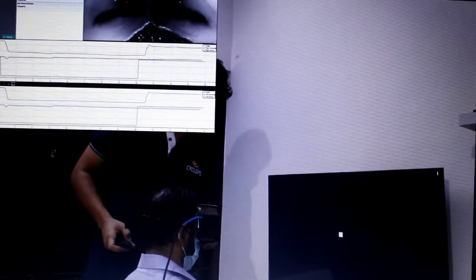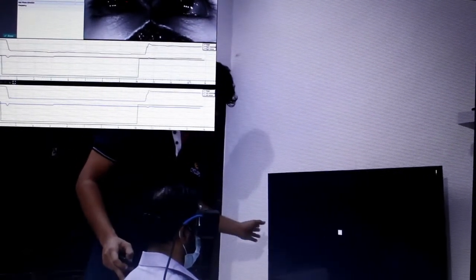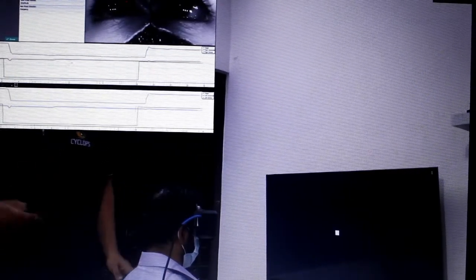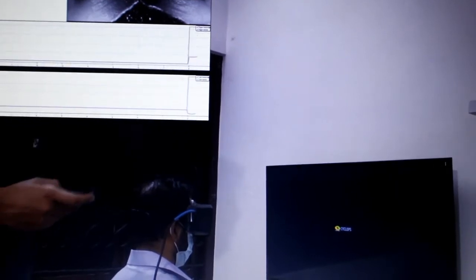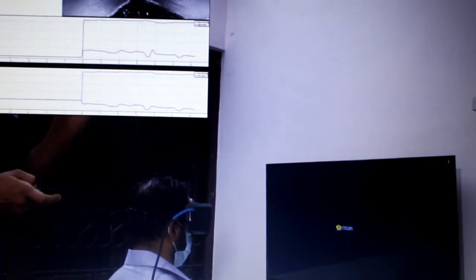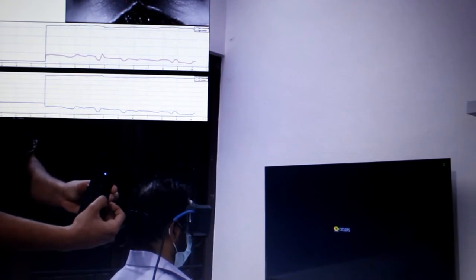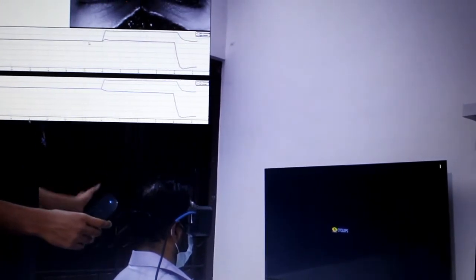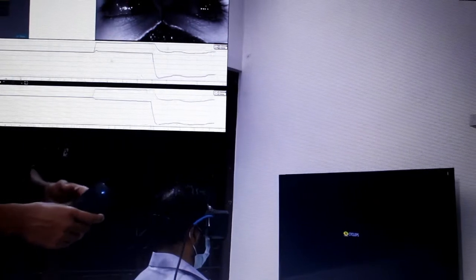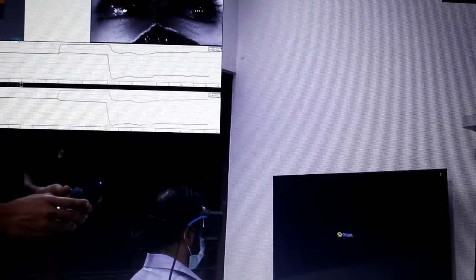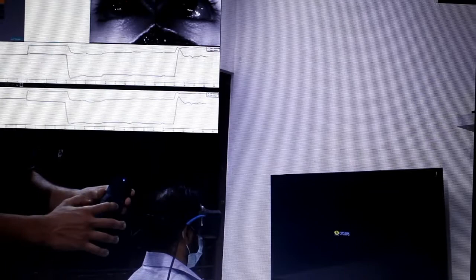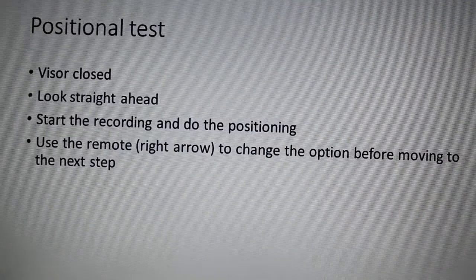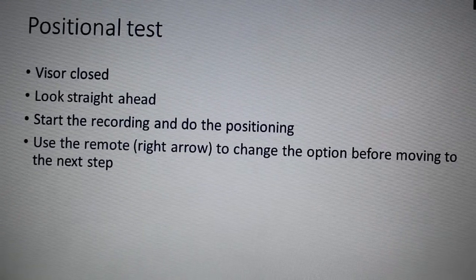For the without-fixation gaze test, close the flap and tell the subject which direction to look. Start with the center/primary gaze for 7 to 10 seconds, monitoring that they are looking straight ahead. Then press the right arrow on the remote to change position. Direct: look left, keep looking left for 7 to 10 seconds. Return to center, press right arrow, and repeat for each position. We are checking gaze evoked as well as rebound nystagmus, so recording at center between positions is important.